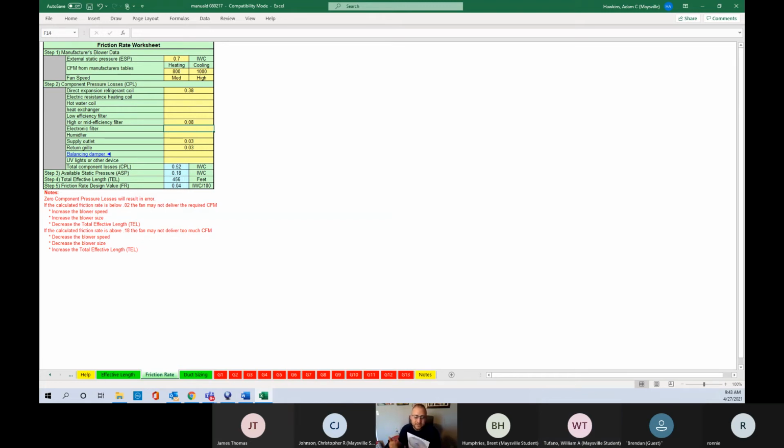So if you start having ECMs, electronically commutated variable speed motors, that are failing, look at airflow, look at duct size, look at filter design, look at coil restrictions, look at all that stuff. Because if they're constantly blowing through motors, or even go through one or two, that's a problem.